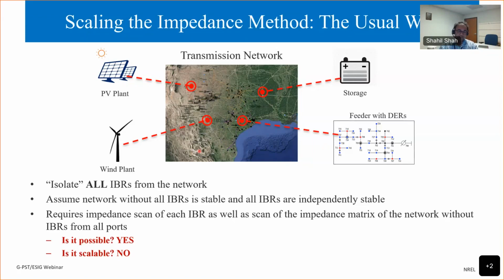Now, we know that in 3-phase power systems, we have 2 degrees of freedom. So each port actually has an impedance which is a 2x2 matrix. For example, in DQ impedance, we have the D axis and Q axis. If we represent impedance using positive sequence or negative sequence, we have again 2 degrees of freedom. So actually we'll need the impedance of this transmission system as an 8x8 matrix. And now if you think about 10, 20, or 100 IBRs, it will be a humongous task to scan the impedance of all IBRs as well as the impedance of the network looking from all those IBRs. So is it possible to scale this? Does it work? No, it's not scalable. So this is not a practical approach.